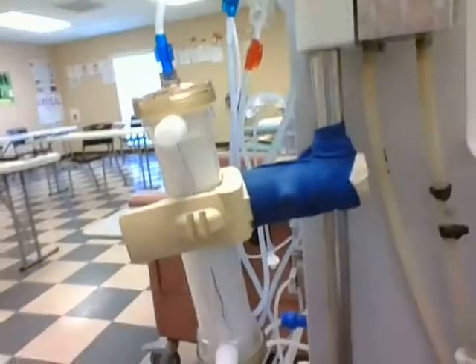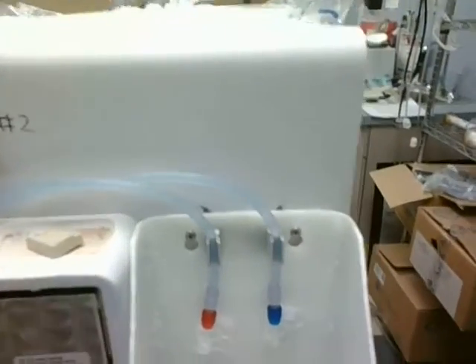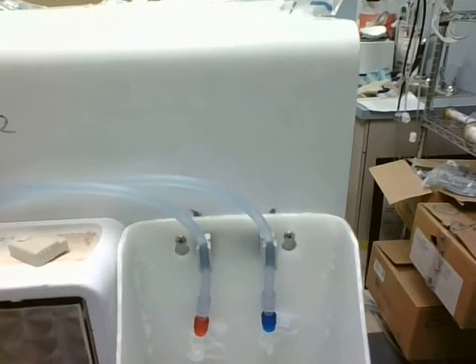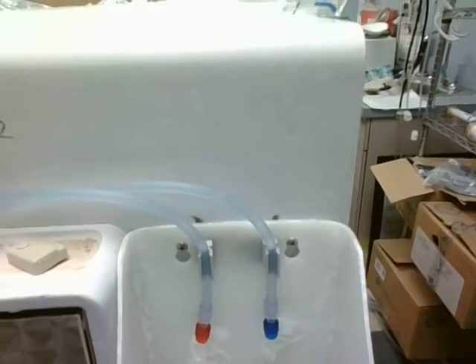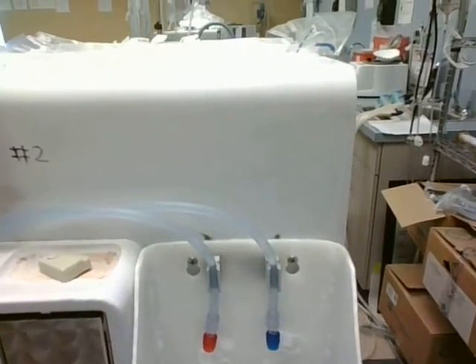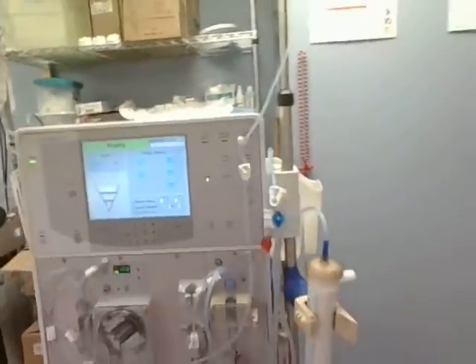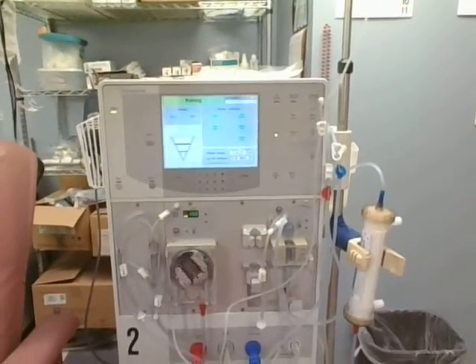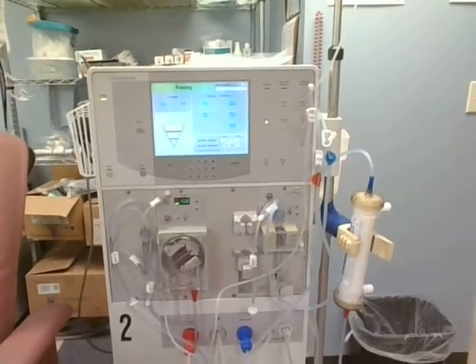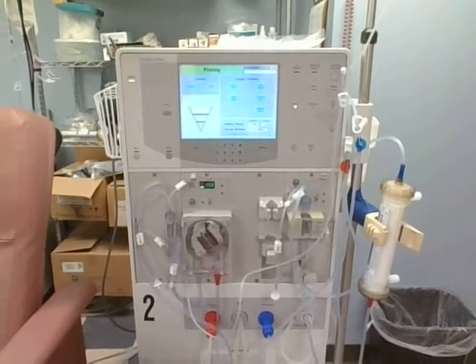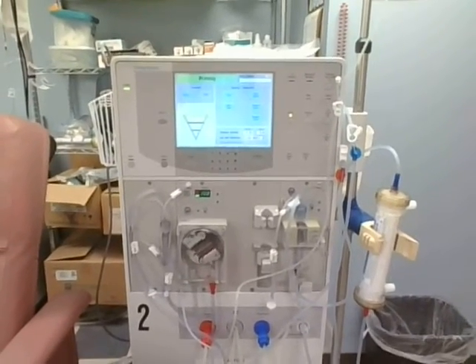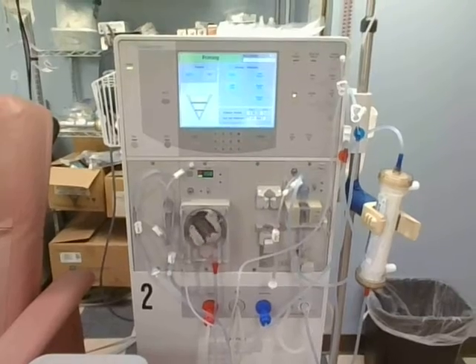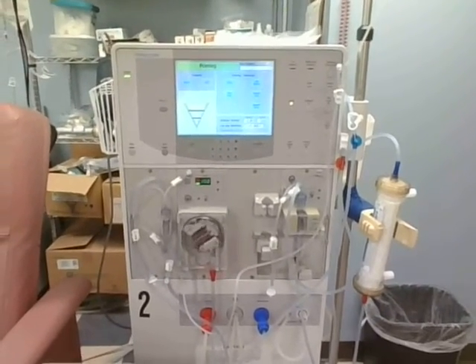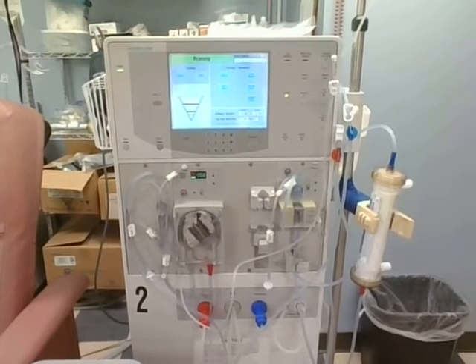As it is going, it will eventually fill up the blood side of our dialyzer, and it's going to start to run out. You can see here the venous line is running out into our drip chamber. All right, this line I do not have to clamp because my machine, this 2008K, is automatically set to prime at 300, which is 300 milliliters. So this machine automatically knows that once it has run through 300 milliliters of fluid, it is going to shut off automatically, and it is going to presume that that line is full.